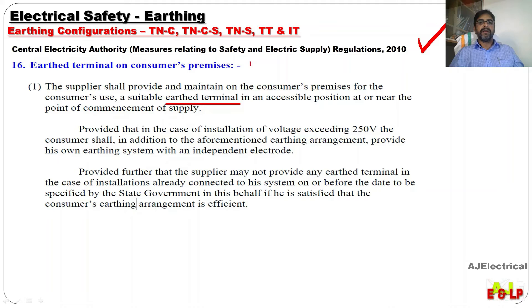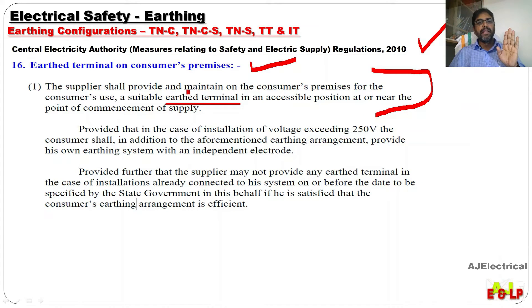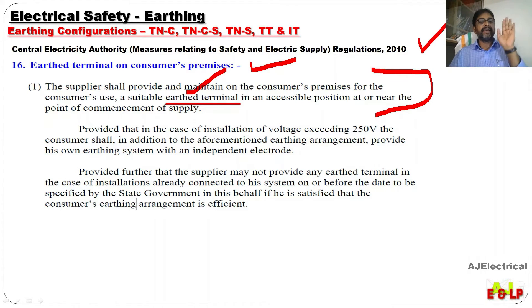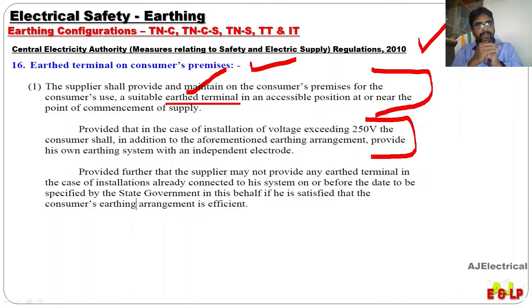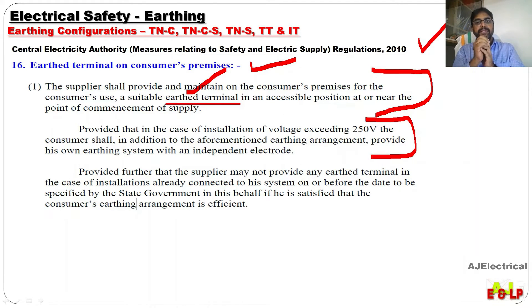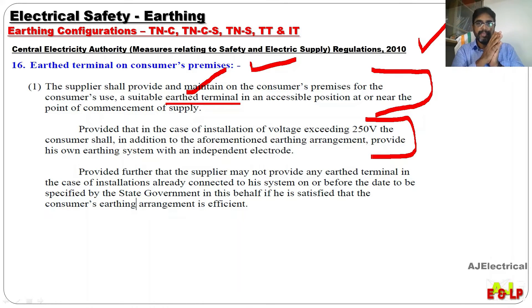Safety Regulation 16 says that the supplier should provide a suitable earth terminal to the consumer. But I am not sure whether we are getting such an earth terminal. Just below that it is said that for consumers having voltage exceeding 250 volt — meaning three phase consumers — they must have their own earthing arrangement in addition to the earth terminal given by the supplier.